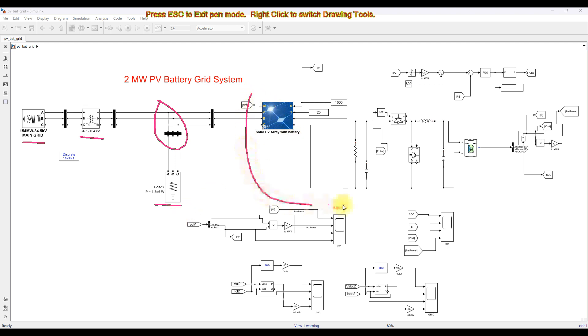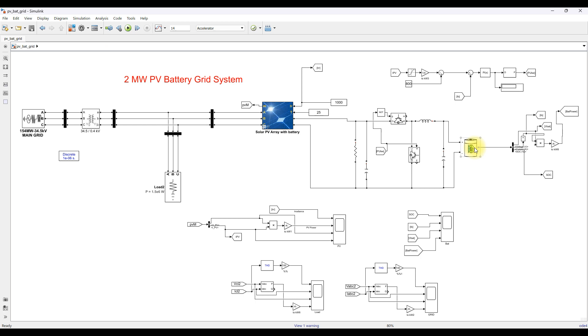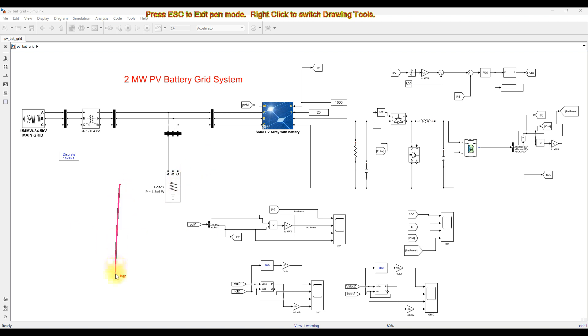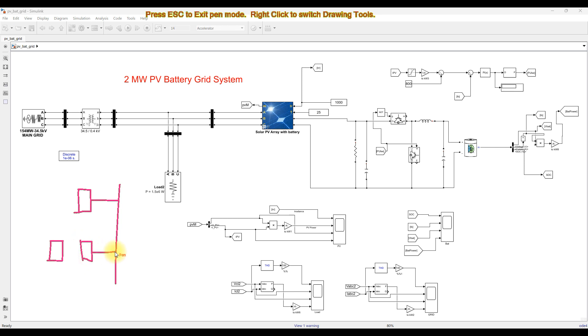Here we have a PV battery system. The battery is connected to the DC link. In this connection structure, the PV is directly connected to the DC link, and the battery is connected to the DC link via a bidirectional converter. After the DC link, we have an inverter for connection to the point of common coupling and the AC grid.